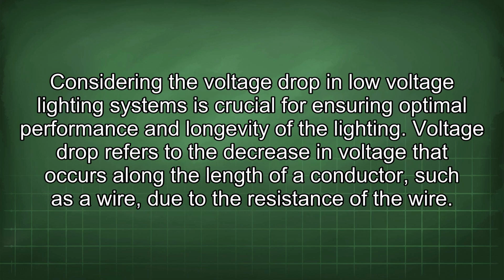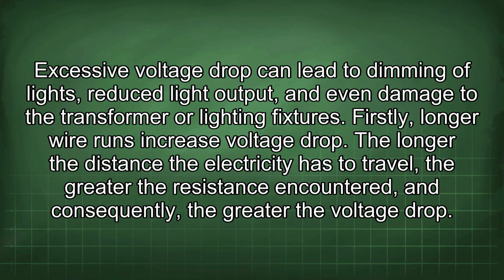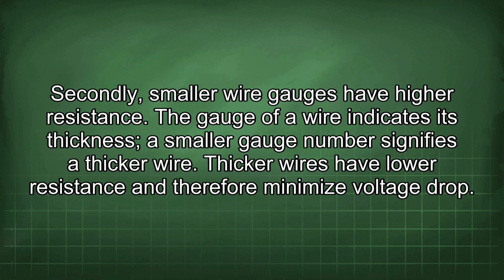Considering the voltage drop in low-voltage lighting systems is crucial for ensuring optimal performance and longevity of the lighting. Voltage drop refers to the decrease in voltage that occurs along the length of a conductor, such as a wire, due to the resistance of the wire. Excessive voltage drop can lead to dimming of lights, reduced light output, and even damage to the transformer or lighting fixtures. Firstly, longer wire runs increase voltage drop. The longer the distance the electricity has to travel, the greater the resistance encountered, and consequently, the greater the voltage drop. Secondly, smaller wire gauges have higher resistance.